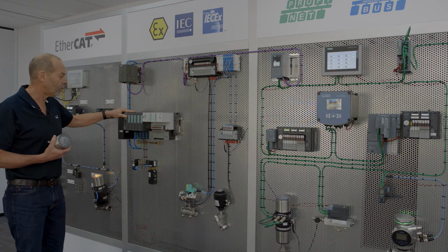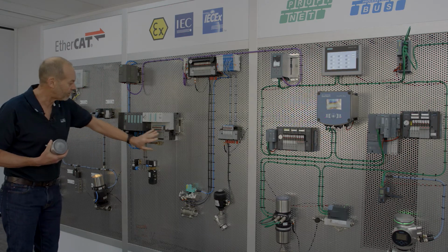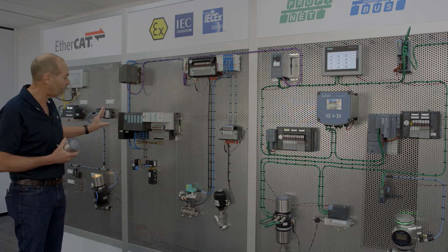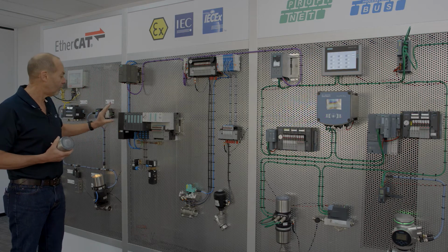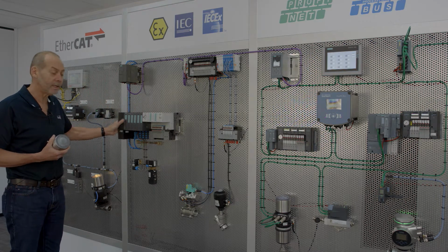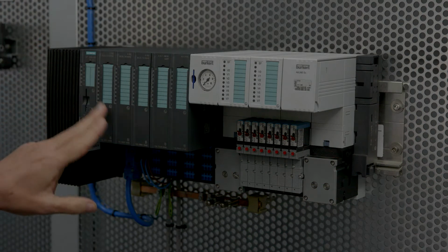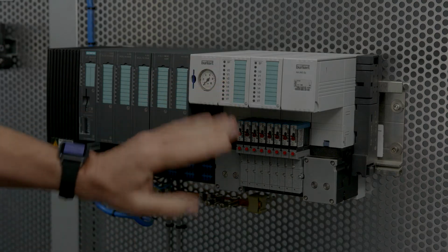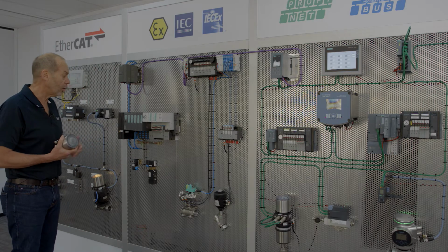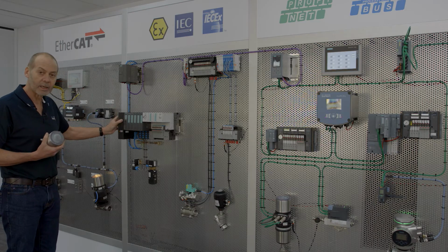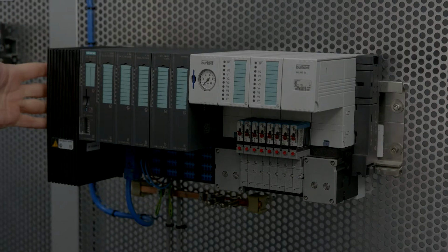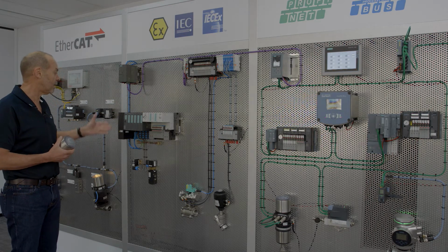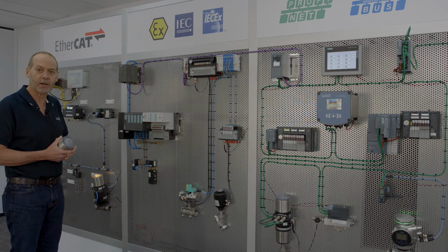For this application, we've integrated the Bürkert valve islands with the Siemens ET200 iSP. This is fully IEC-Ex certified for installing in a Zone 1 area. It incorporates whatever inputs and outputs you want: digital in, digital out, analog in, analog out, and of course valves. You can put that directly into an increased safety enclosure in the Zone 1 area. I'm going to hand over now to Nelson, who's going to take you through the integration of this system into the TIA Portal.